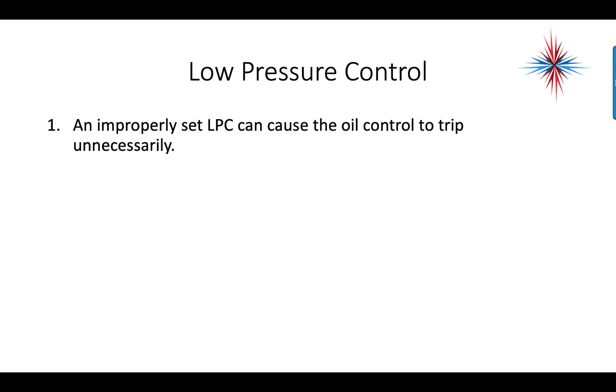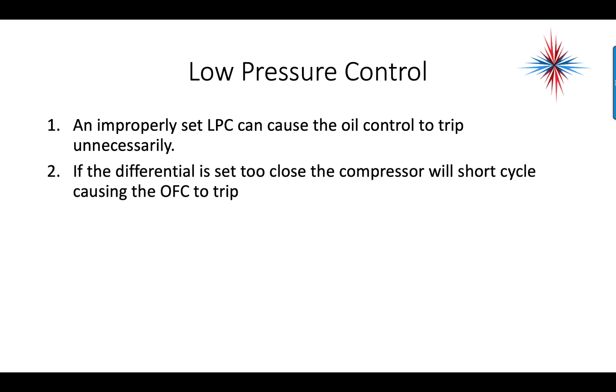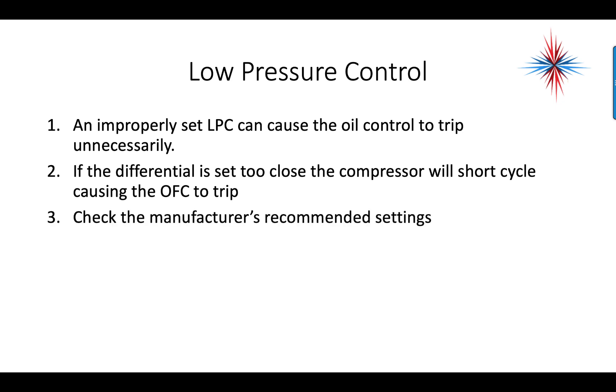An improperly set low pressure control can cause the oil pressure control to trip unnecessarily. If the differential is set too close, the compressor will short cycle, causing the oil failure control to trip. Check the manufacturer's recommended settings for low pressure controls.